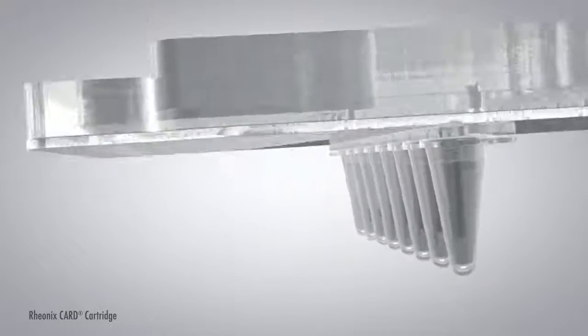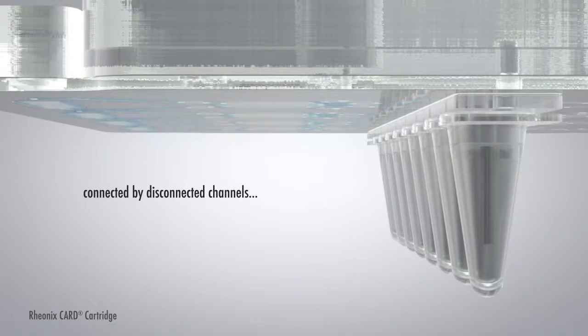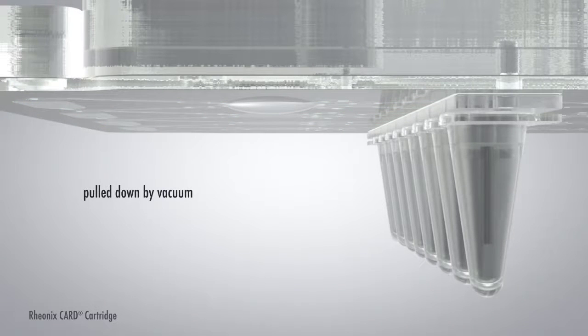The movement of fluids within the card is mediated by microfluidic channels and diaphragms integrated into the lower surface of the device. The Encompass MDX sequentially applies positive and negative pressure to the diaphragms, which causes fluid to be pumped through to the various steps of the assay.